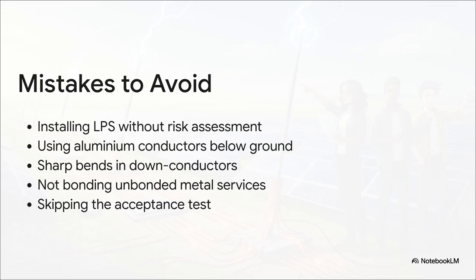Number 3, putting sharp bends in your down conductors. Doing that creates high impedance, literally choking the path to the earth. Number 4, failing to bond all metallic surfaces at the zone boundaries. That allows really dangerous potential differences to build up. And finally, never ever skip your final 3-point fall of potential acceptance test. I mean, a pristine design on paper means absolutely nothing if you don't measure the actual earth resistance in the field.